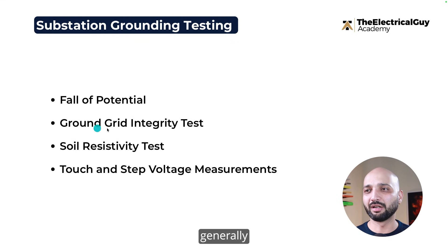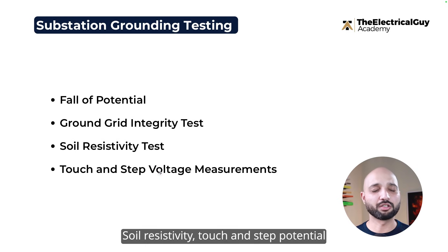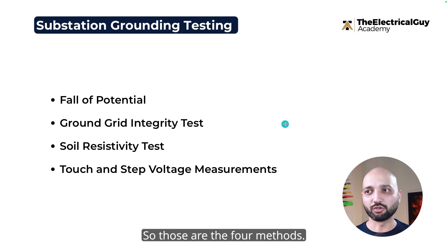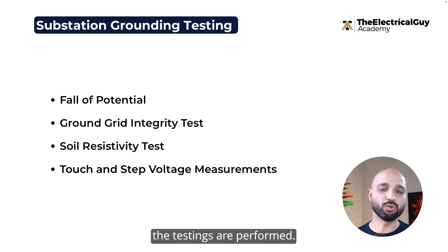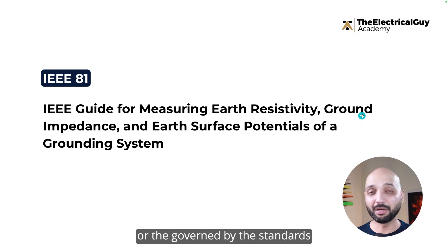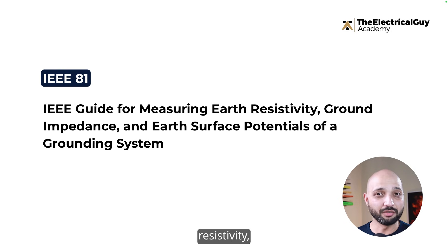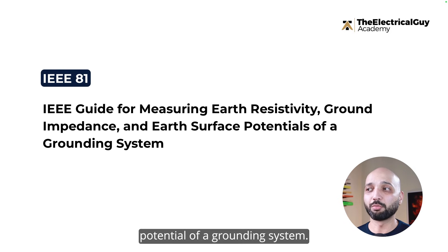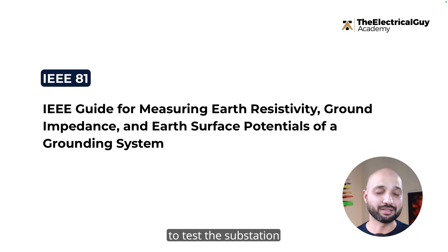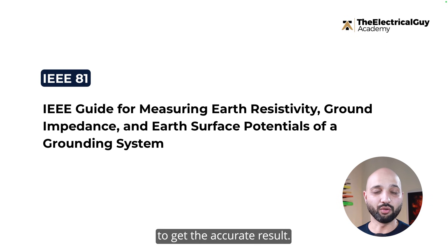Among these four methods, the first two are most commonly used. Soil resistivity and touch and step potential can be performed for a greenfield project — that means a substation that is being newly built. All these testings are generally governed by standards like IEEE 80 and 81, which provide the guide on measurement of earth resistivity, ground impedance, and earth surface potential of a grounding system. These standards define the steps that must be followed to get accurate results.